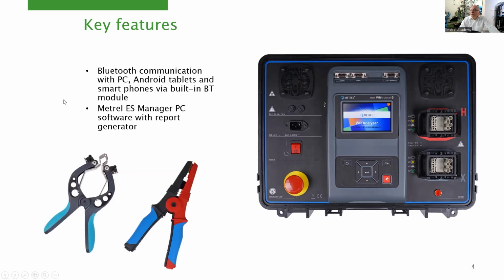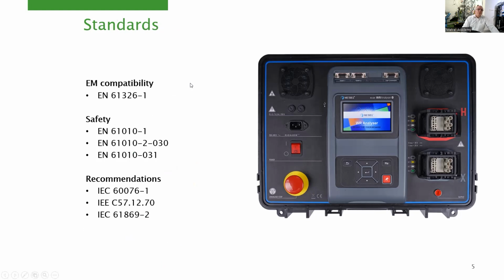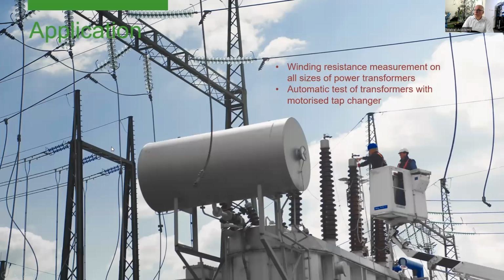The instrument is also supported with all the needed accessories and PC software, and the communication can also be via Bluetooth. For sure, we comply with all the needed standards for safety and recommended functional standards. So go to the next. As I mentioned, there are actually no limits for these instruments in the size of the transformers. So we can test from small distribution transformers up to big transformers in the transmission network, power network.